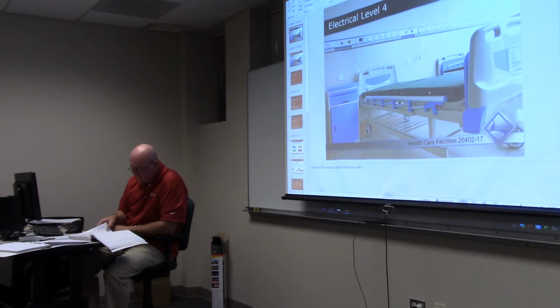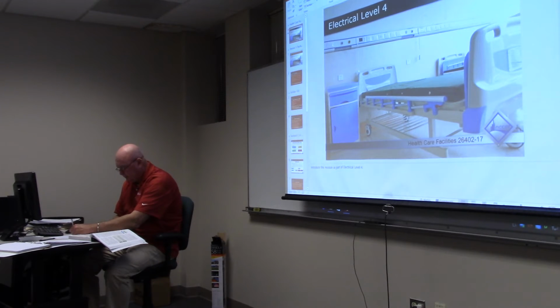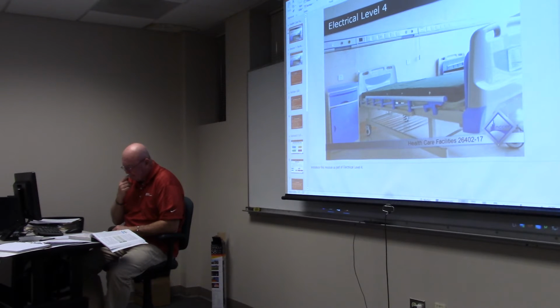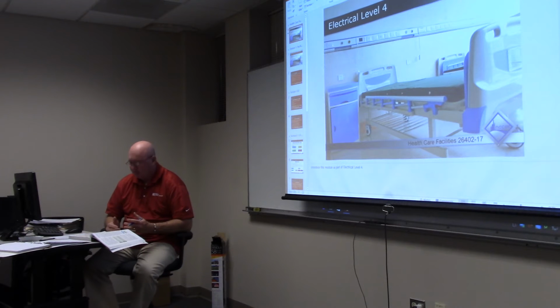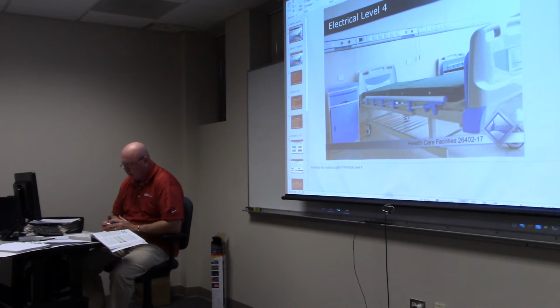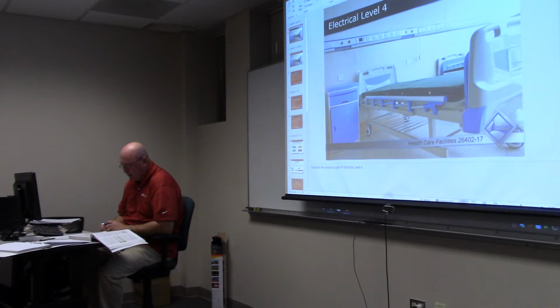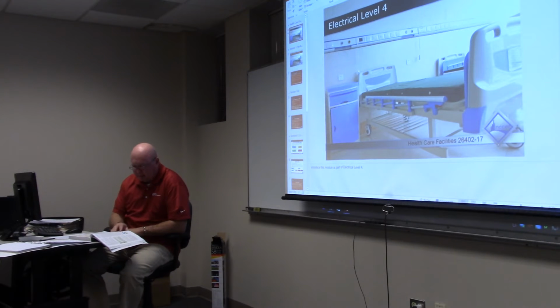As specified in NEC 517.14, where branch circuit panel boards for normal and essential power serve the same patient care vicinity, they must be connected together with an insulated copper conductor no smaller than a number 10 AWG. Number 10, AWG. Okay. And we'll talk about why that's important, about why they're connected together, as we get into our book. All right, number 7, Cameron.